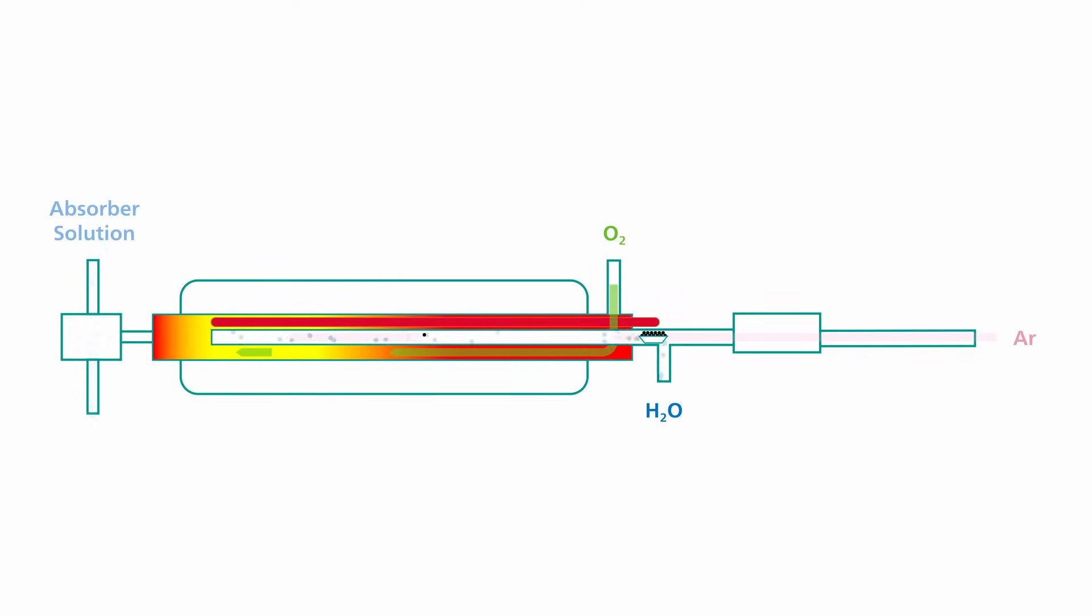Argon is continuously flushed through the system to transfer the volatilized sample into the absorption solution. The addition of oxygen and water during combustion guarantees complete combustion of the analytes and the release of the organohalogens from the activated carbon.